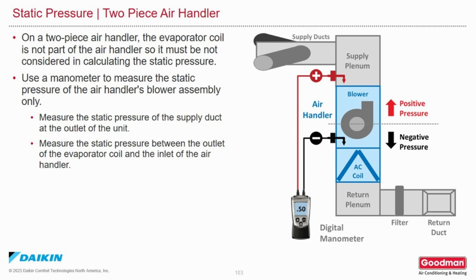When you're measuring the static pressure of a two-piece air handler, the evaporator coil is not part of the air handler, so it must not be considered in calculating static pressure. Use a manometer to measure the static pressure of the air handler's blower assembly only. For positive pressure, measure the static pressure of the supply duct at the outlet of the unit in the supply plenum. For negative pressure, measure the static pressure between the outlet of the evaporator coil and the inlet of the air handler.